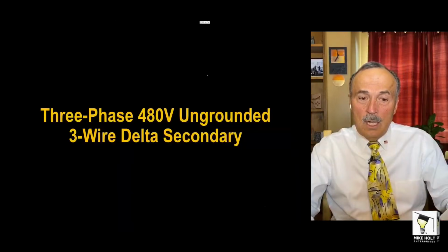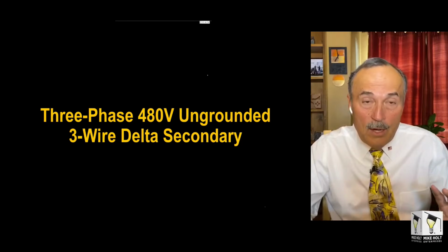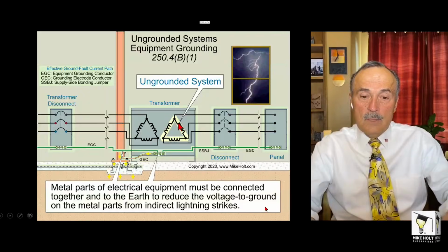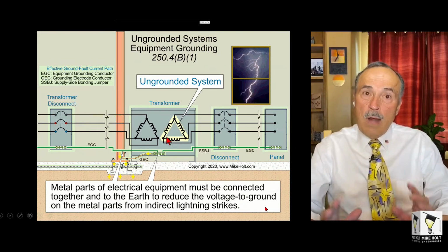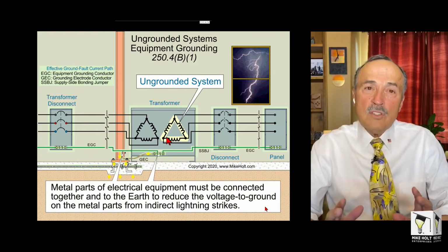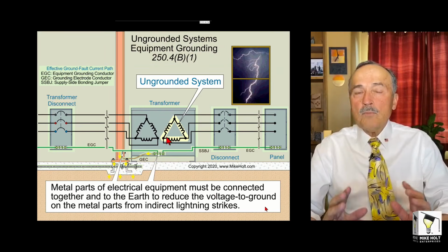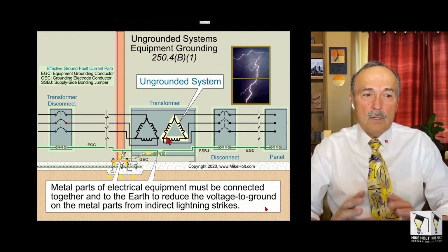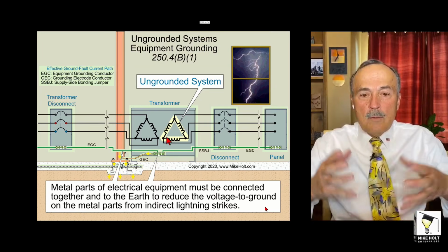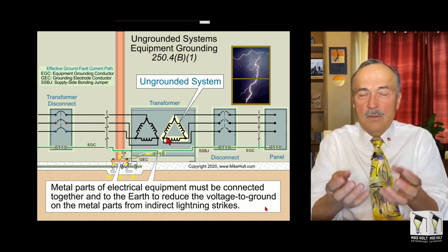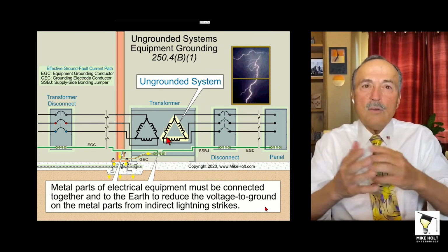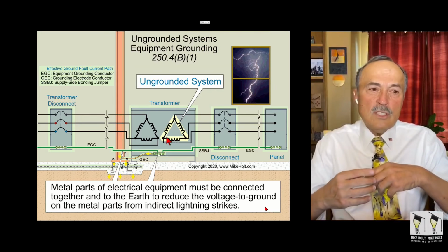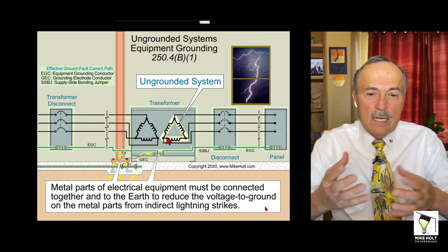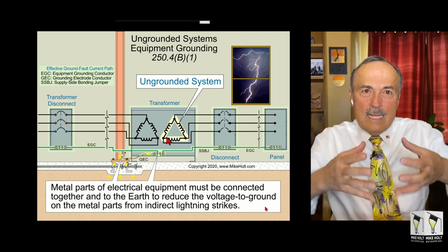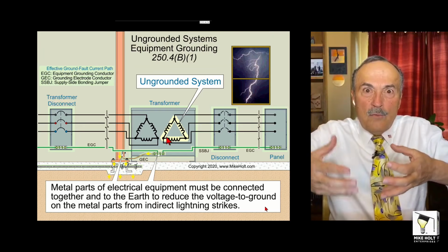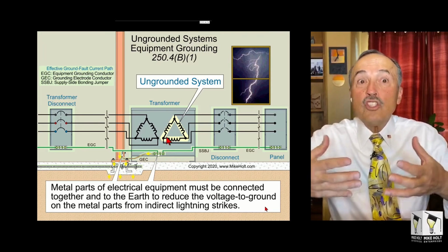I love it. Three-phase, 3-wire, 480 volt ungrounded system. Well, here's your ungrounded system. The problem with ungrounded systems is, I won't say they're unstable, but Beeman talks about 8 or 9 different scenarios where, when you have a floating system like this, there are restriking ground faults, there are ferroresonance conditions, and there's lightning and static. This insulated winding and all the insulated conductors are kind of floating in the air, and they end up getting a charge.